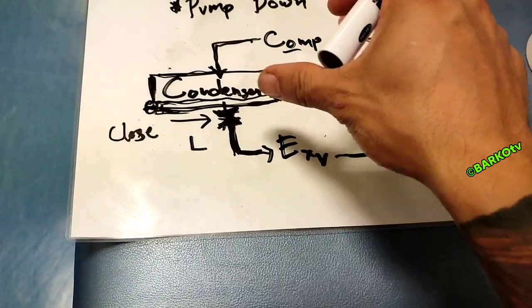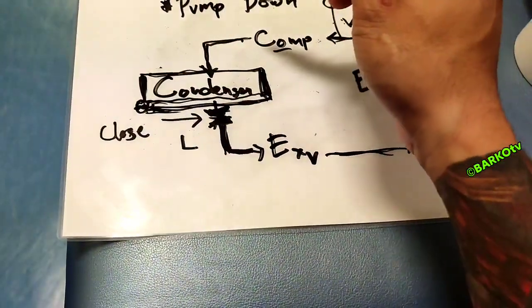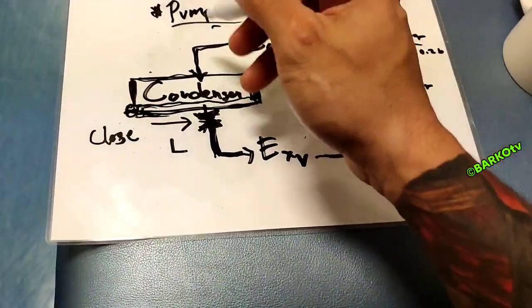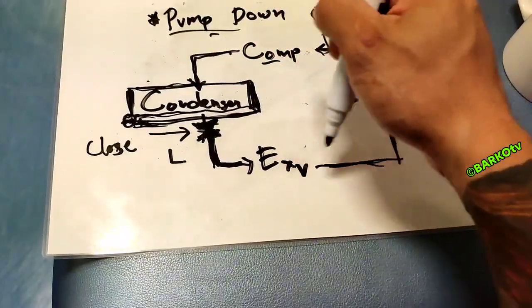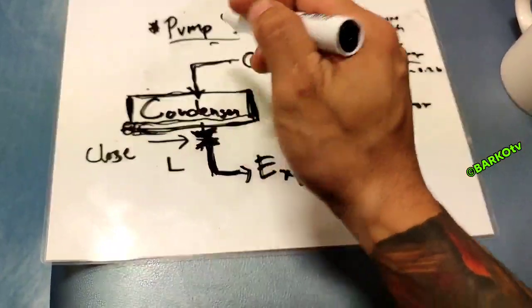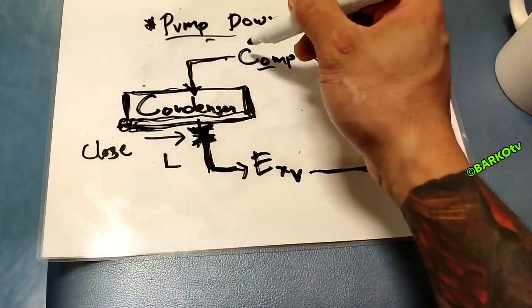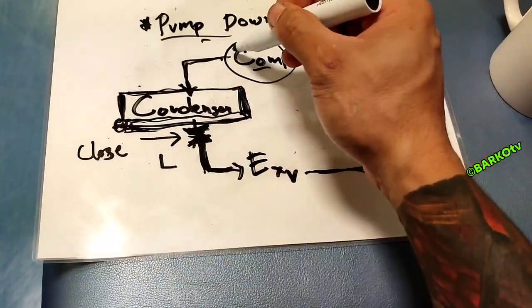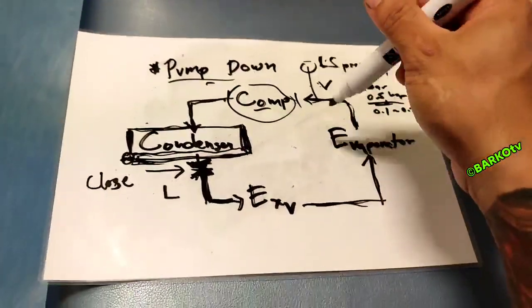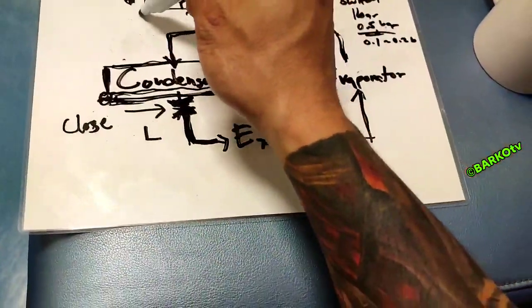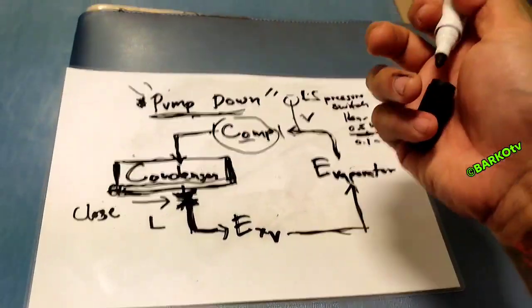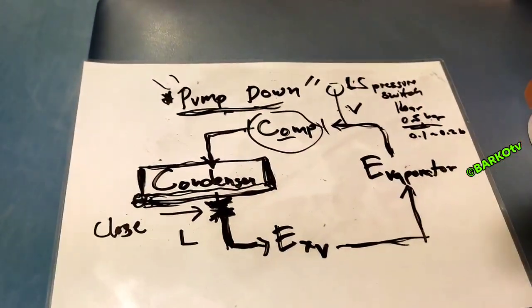This is the manual pumping down procedure when you have maintenance on your compressor. After pumping down, you close the suction and discharge valves on your compressor. Then if you plan to change the oil, you drain all the oil and clean the compressor.